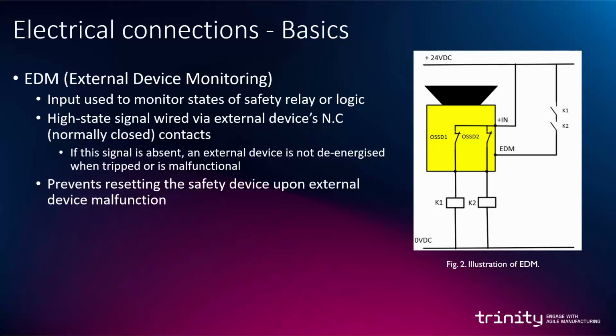The EDM or external device monitoring is an input used to monitor the states of an external safety device, such as a safety relay or logic. The EDM input should be wired as a high state signal to the external device's NC or normally closed contacts. This means that the EDM input upon a safety violation becomes energized with 24 volts DC. And if this signal is absent, an external device is not de-energized properly when a safety violation occurs or the external device is malfunctional.